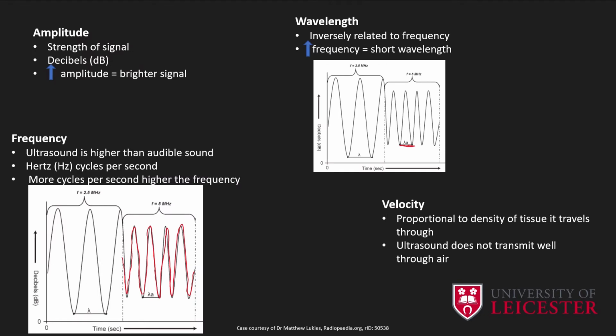If we want to be able to understand what we're seeing on the screen, we need to understand what these four physics principles are. Amplitude in audible sound would be referred to as the loudness or the strength of the signal. It's measured in decibels. The higher the amplitude of the transmitted signal, the higher the amplitude of the return signal. The return signal is assigned a pixel value, which is displayed on the screen. So the higher the amplitude, the brighter the image.